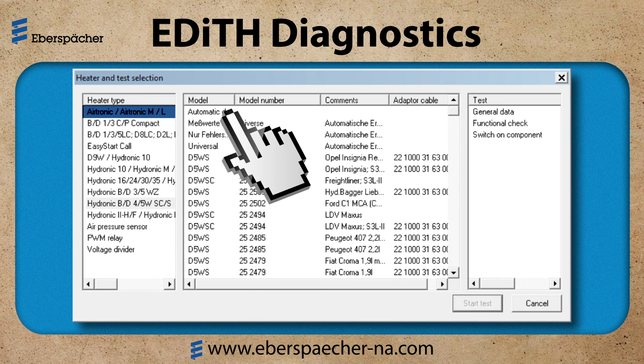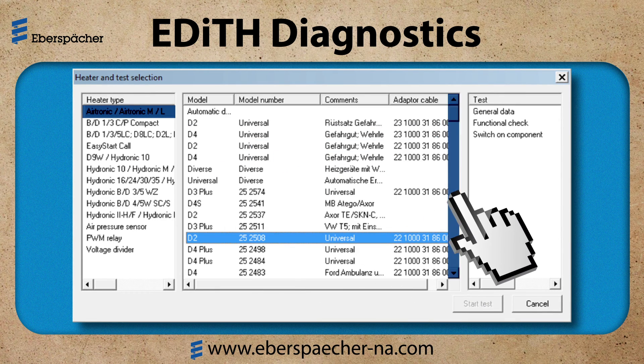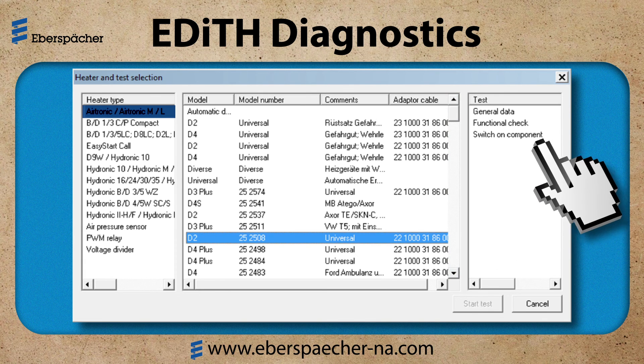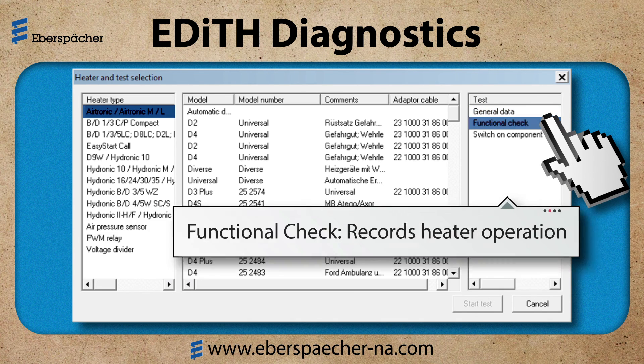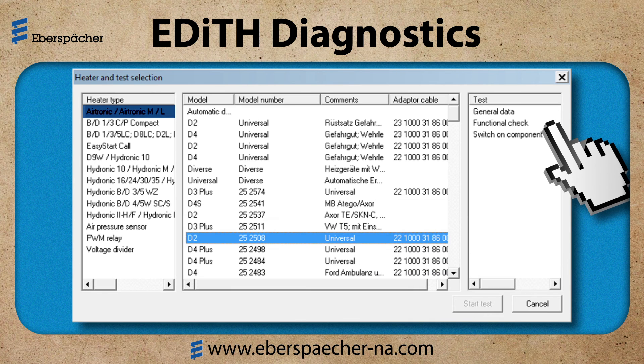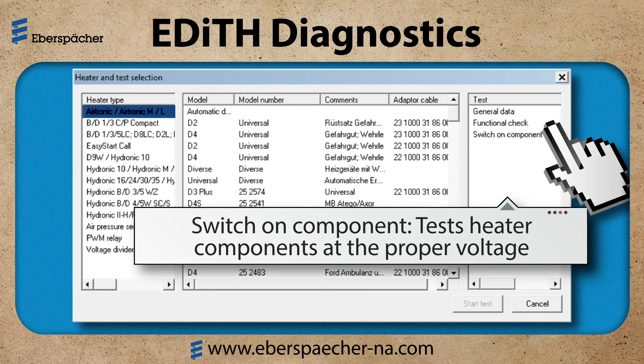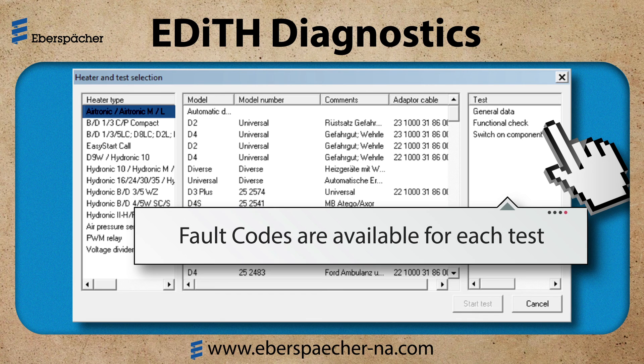Next, select the automatic detection line at the top of the model selection, or you can use the scroll bar and locate your model number off the heater. The following tests are available: General Data shows the operating hours; the Functional Check, which records the heater operation as long as it is active and connected to EDITH, whether it be three minutes or three hours; and the Switch On Component, which tests the heater components at the proper voltage. The error tab or fault codes is available on each test.